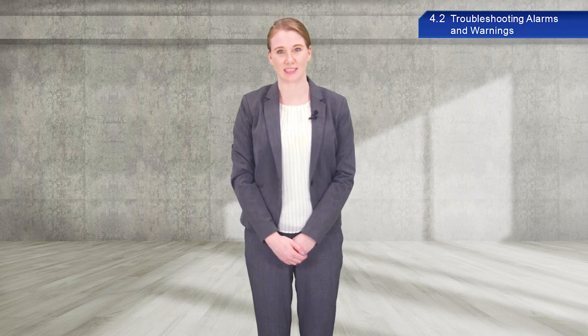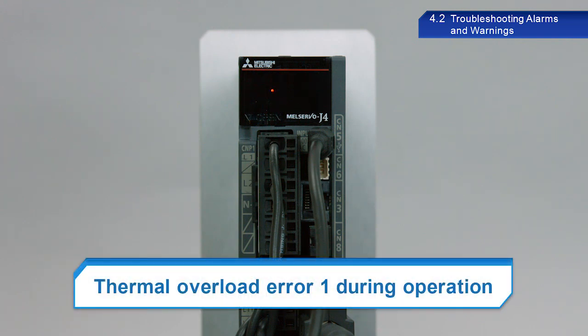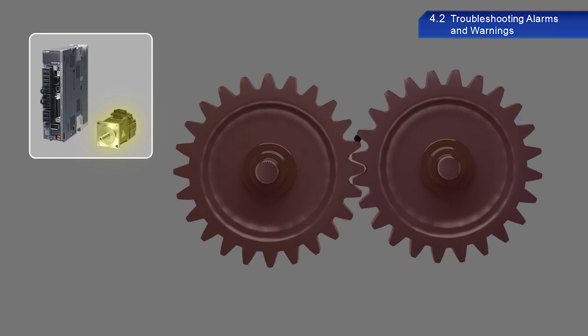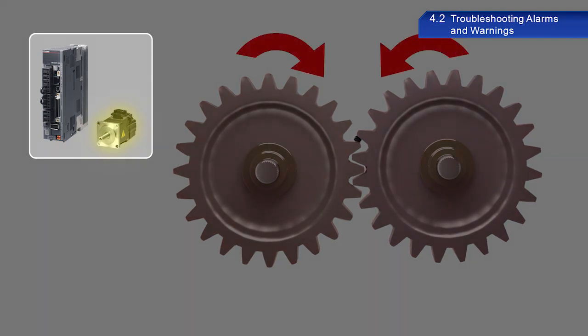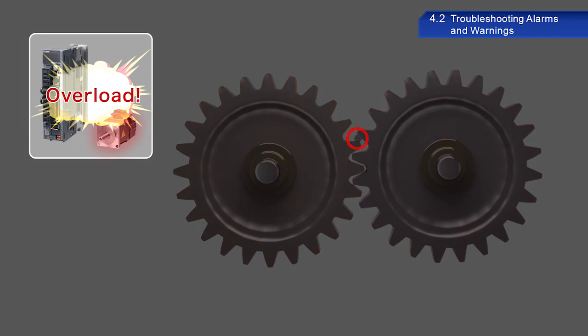Besides noise, harmonics and leakage current can also negatively affect servo systems. Alarm code 50.1 is the Thermal Overload Error 1 During Operation alarm. This alarm occurs when cables are disconnected or scrap material is jamming equipment. Objects can jam moving parts, causing excessive current to be output to try and move the part normally, which causes excessive load and triggers this alarm. If this happens, check mechanical parts carefully. If this alarm occurs when there are no mechanical issues, wiring may be disconnected or connected incorrectly, so check the wiring.